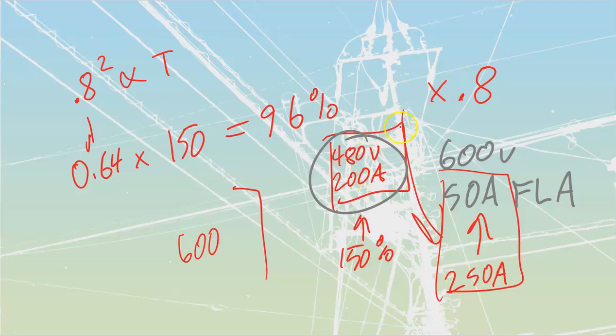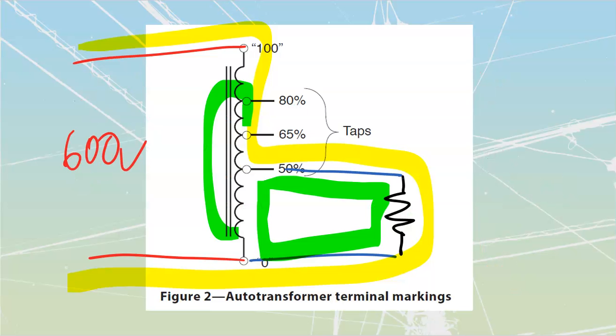So what I can do is say kVA out, 480 times 200, is going to have to be equal to my kVA in on the high side. Just take your 480 times 200 times root 3. That's going to give you your motor kVA, and then take that and divide it by 600 times root 3, and that's going to tell you that your line side current coming into this autotransformer is going to be reduced down to 160 amps.